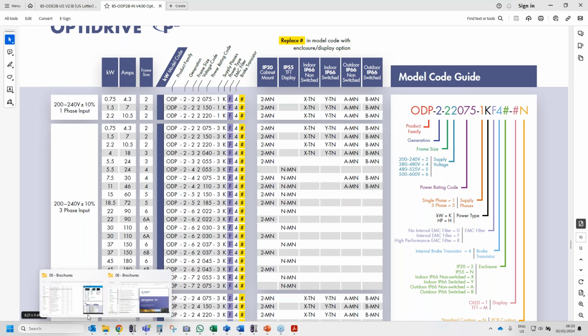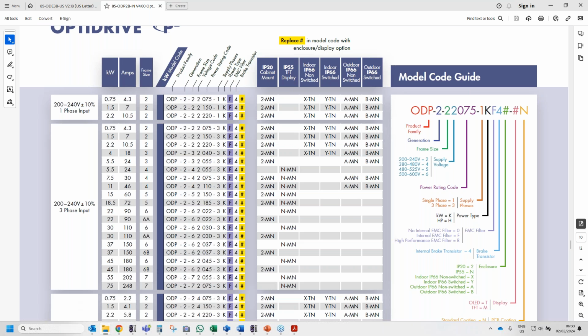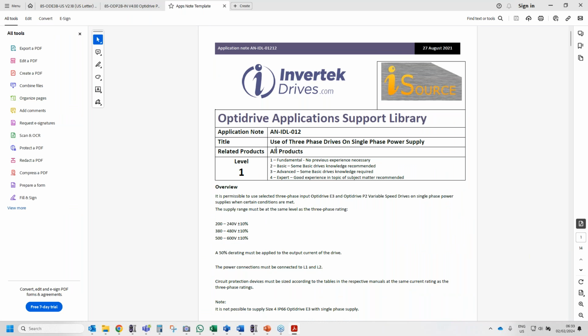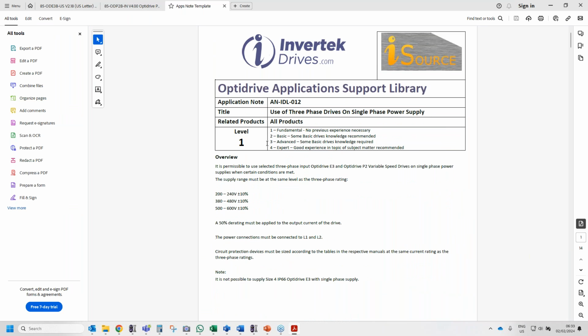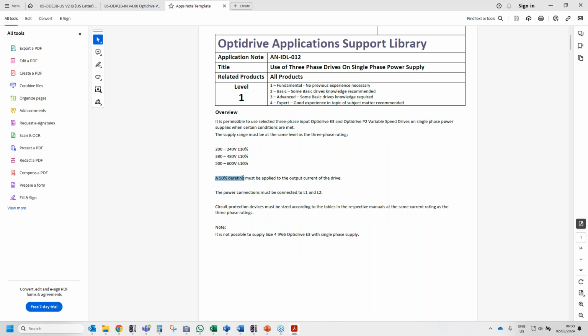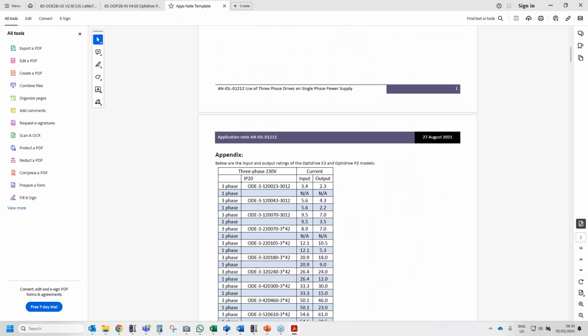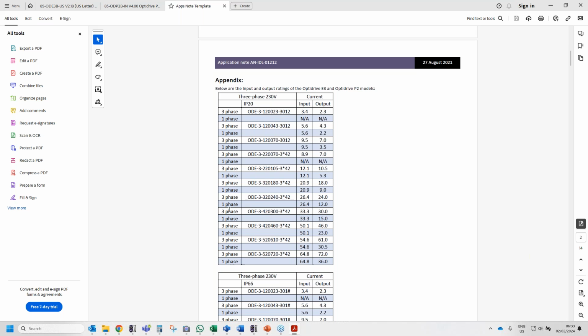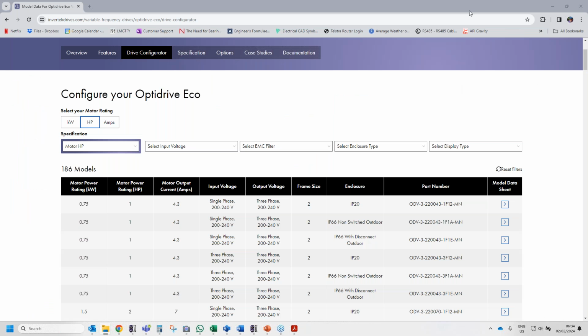As I said, we have application notes. Let me open up the application note for you on that. This is an example, the use of 3-phase drives on a single phase power supply. These are the ratings that we can do, and then a 50% derating must be applied to the output current of the drive. There's the 3-phase rating, single phase rating, the input current and the output current available. So it's possible to do that up as high as 15 horsepower. Okay, is that okay for you?